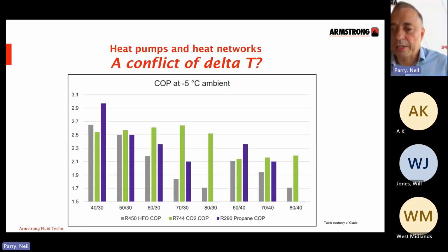So a couple of comments I've had: isn't there a conflict between the delta T's of the network and the heat pump? Well, the previous slide has hopefully shown how you can address that issue at the heat source itself, at the heat pump itself, without compromising there. But with the latest generation of CO2 heat pumps, we can see that they not only can work on the significant delta T's that you hopefully can achieve on your heat network, but they also allow higher flow temperatures as well. So they are more suitable for existing buildings, which, if we're going to get to net zero by 2050, we absolutely need to address, our existing building stock. Well, here's a way of doing it with maybe a CO2 heat pump.